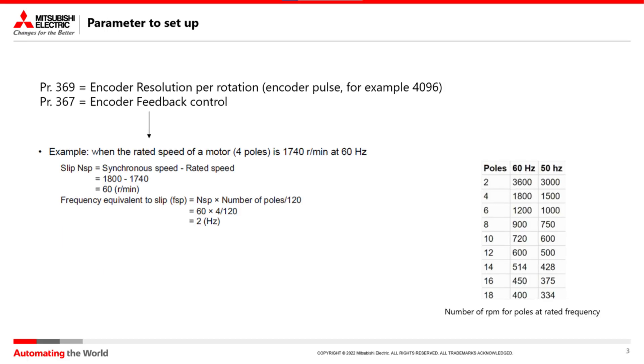The inverter parameters to be modified are parameter 369 and parameter 367. Parameter 369 indicates the encoder resolution for rotation — that is, the encoder pulses per revolution.